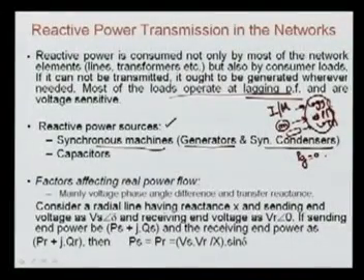It is an alternator which is generating the reactive power, but the P generation is 0, means there is no electrical power generation. It is simply running and improving the reactive power, then it is called a synchronous condenser. Normally it is not true, but what we do, we can have a synchronous motor where the mechanical load is 0. Basically condensers are the motors where there is no load on that motor, but it is rotating and we are just providing the reactive power to the system to improve the voltage profile of the system.